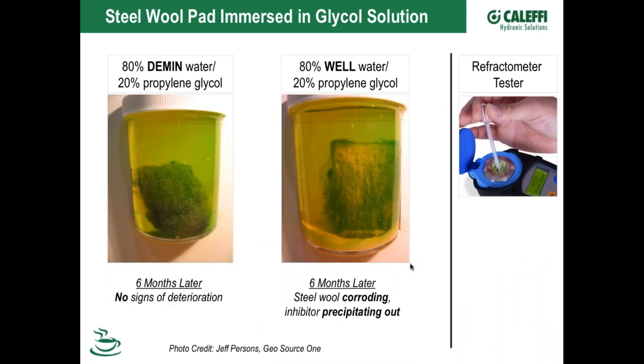I think Jeff Persons gave us these slides. This is an example of exactly what happens when you take good glycol and mix it with demineralized water - a steel wool sample was put in there, and after 6 months it looks pretty good. Here's that same propylene glycol mixed with well water that probably had a lot of hardness or TDS in it, and you can see the difference in the reaction of the steel wool because you didn't use good quality water when you built that glycol - it's starting to break down that fine steel wool.